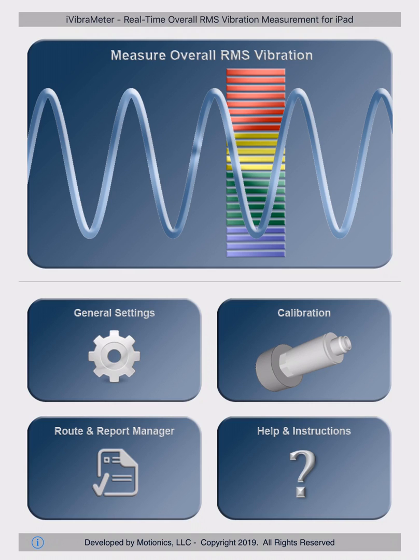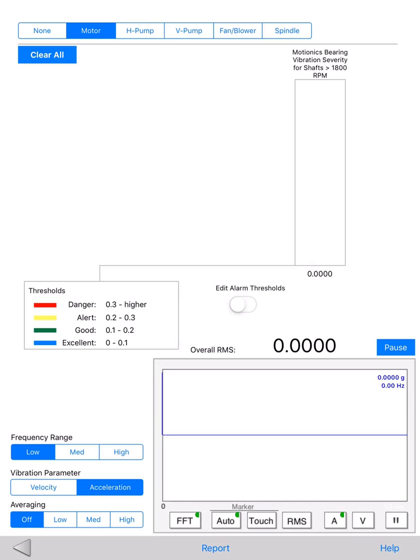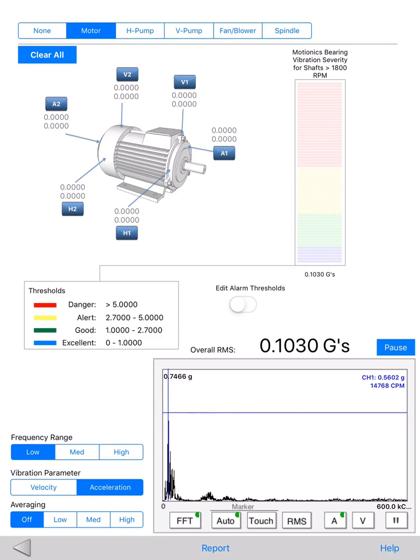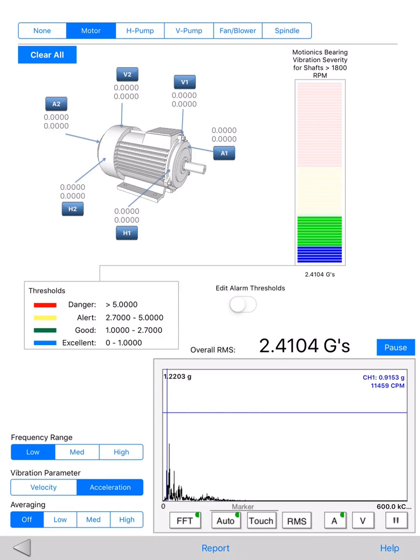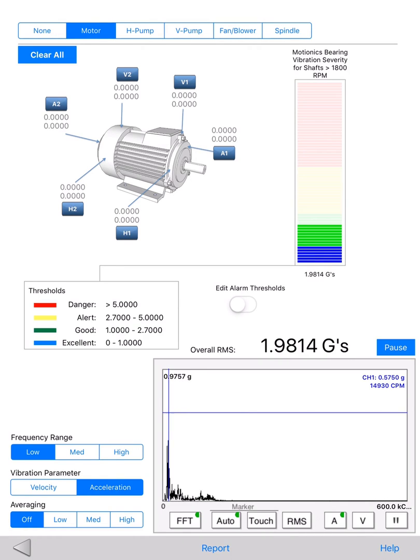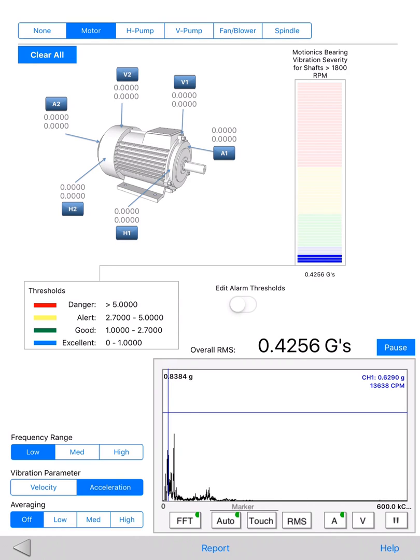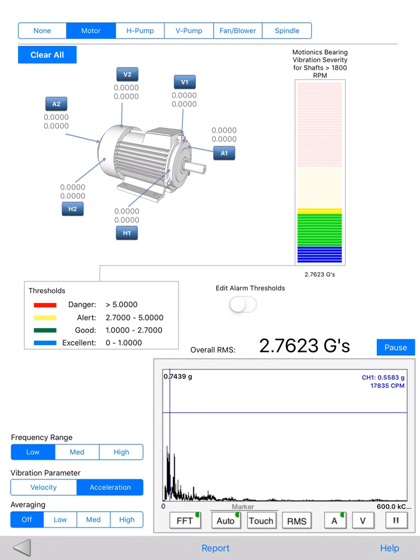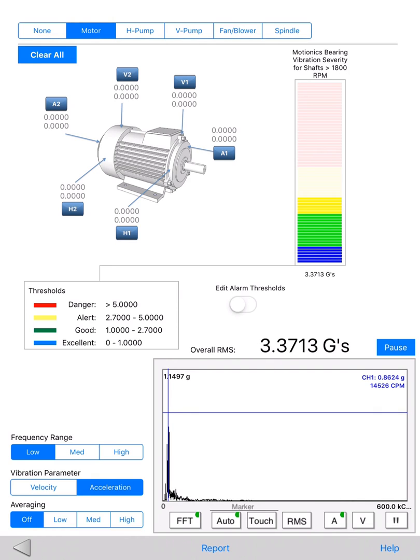The first page I'll visit is the overall vibration measurement page. This page can be divided into two parts: the top part is for capturing overall vibration readings, and the bottom part has a real-time vibration signal viewer.